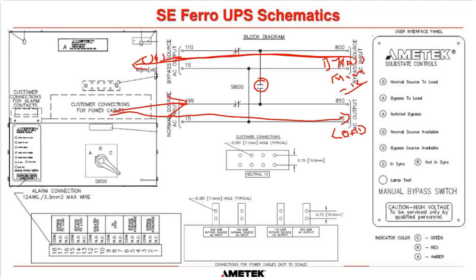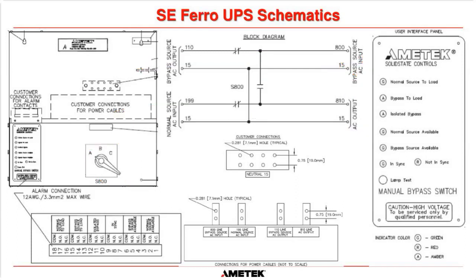Okay. The RMBS has a 3-position rotary manual handle on the front of it. There is no automatic function in this whatsoever. This is a rotary switch. And then we have this mimic panel or front LED panel, and it shows you what's on the front. Once again, green, red, amber. So you should only have green lights. So you say normal source to load, normal source available, bypass source available, and in sync. Those are the alarms that should be on your RMBS at all times.